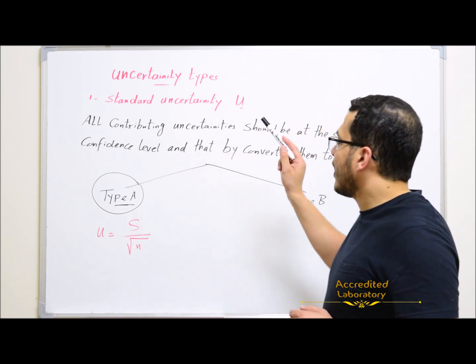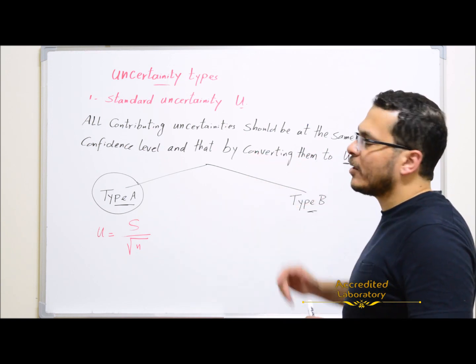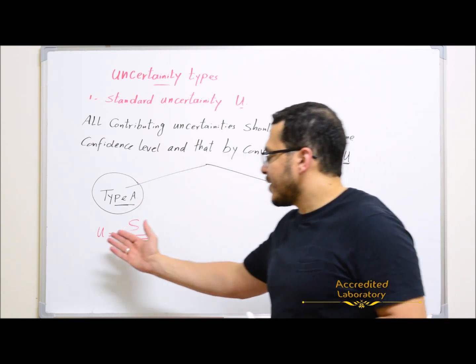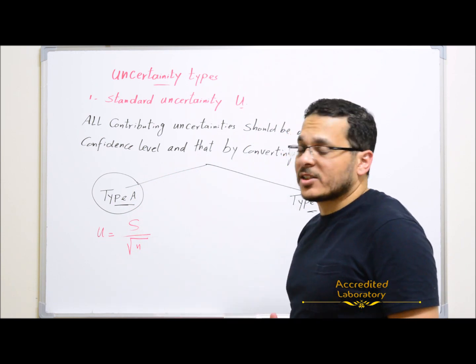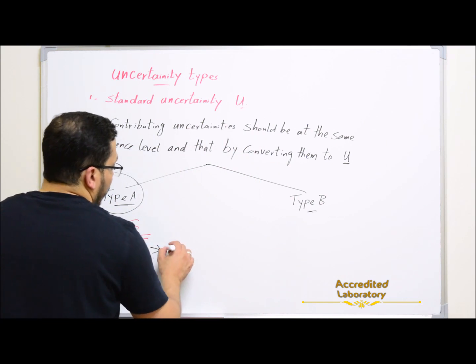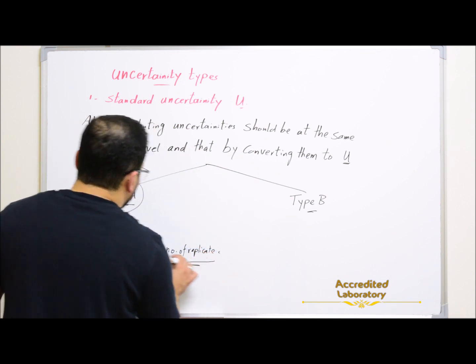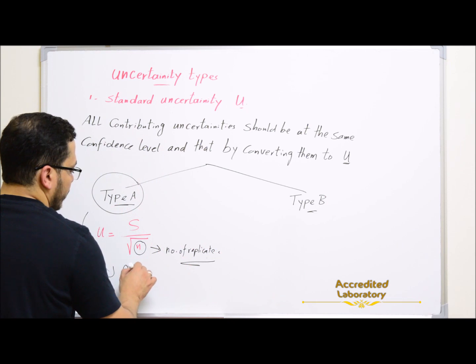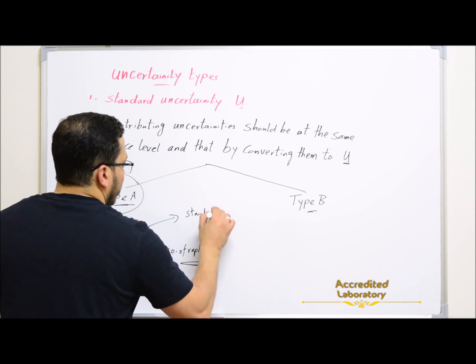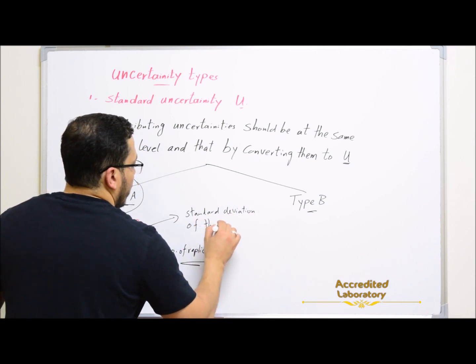All contributing uncertainties should be at the same confidence level, and that will be done by converting them to standard uncertainty. In case of Type A evaluation, standard uncertainty equals standard deviation divided by the square root of n, where n is the number of replicates, because only in this case do you have repeatability. This gives you the standard deviation of the mean.